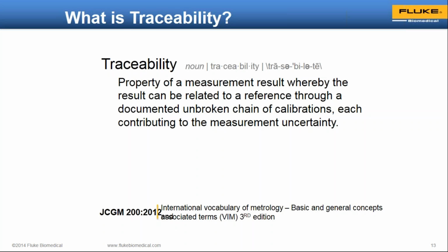And here's the reason: your measurements also must be traceable. And this is coming to you. We're trying to improve how we teach about this because there is a new International Organization for Standardization standard called 17025. In a short time, 17025 is going to require even you to report both your uncertainties and your traceability path in order to properly and completely document that you are making sure that the medical devices are safe and effective for clinical use. Believe me, this is coming. So traceability and the concept of uncertainties are very important for you to begin to understand.